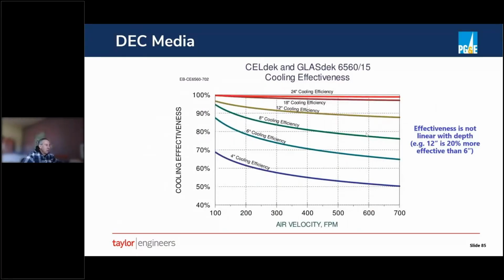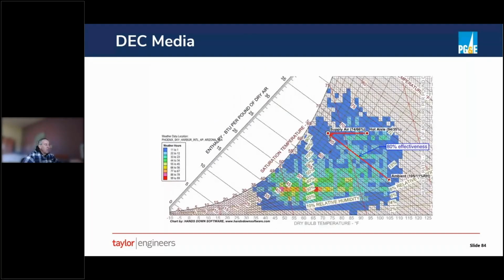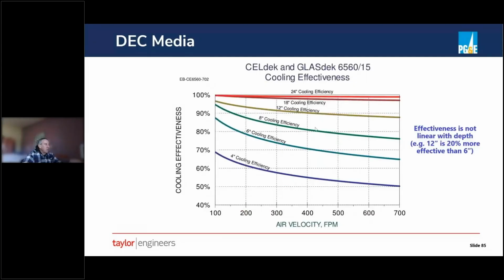Some more characteristics about the media. It comes in different thicknesses. As it gets thicker, as you can imagine, the effectiveness improves. And the effectiveness is basically how far from whatever condition you start at, how close can you get to this saturation line? 80% effectiveness means you can get 80% of the way from here to there. And that may be more than you need, but there may be cases where you need that level of effectiveness. And so if you need more effectiveness, you can increase the thickness of the media. There's a diminishing return. The effectiveness is not linear with the depth. So for example, 12-inch media over here is only 20% more effective than, say, 6-inch, right? You might go from 70% to 90% at a velocity of 500 feet.